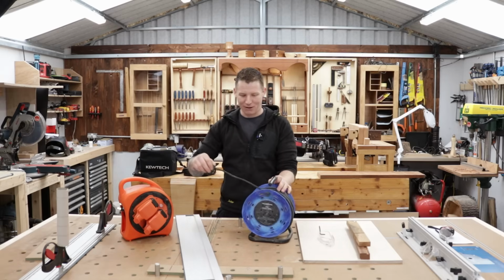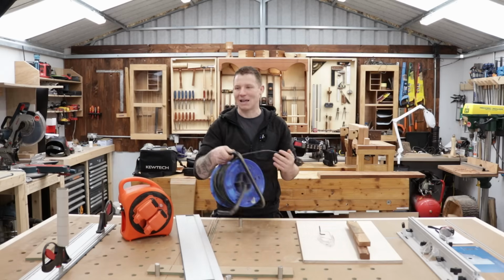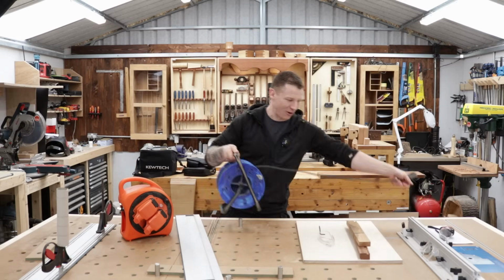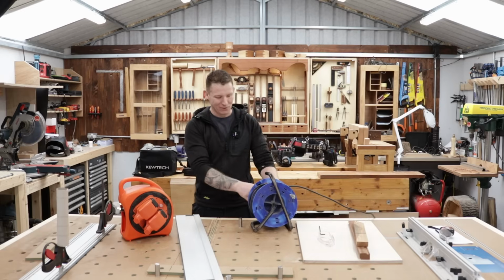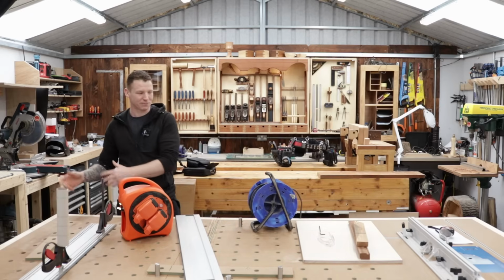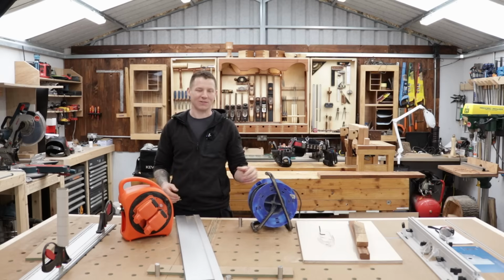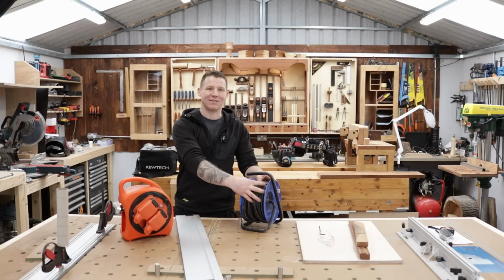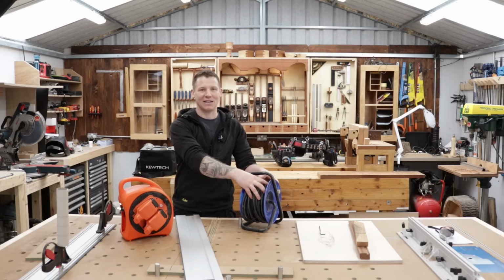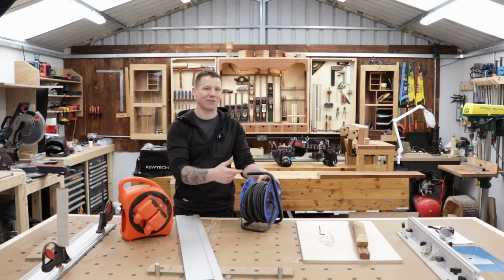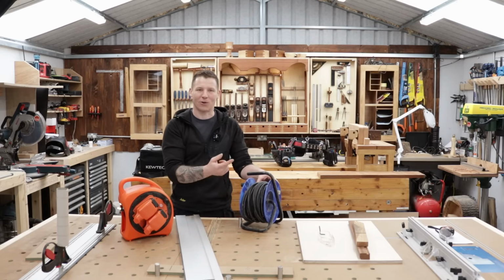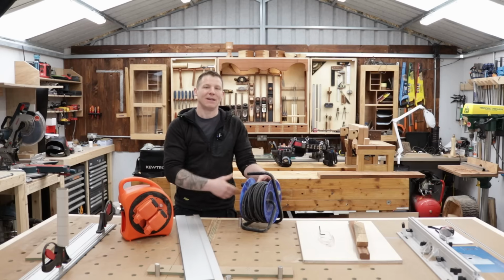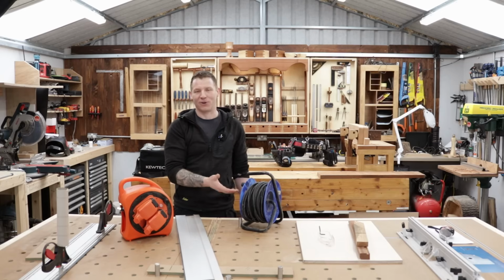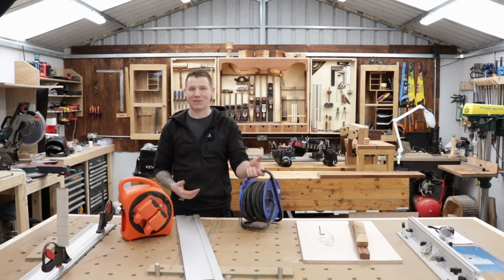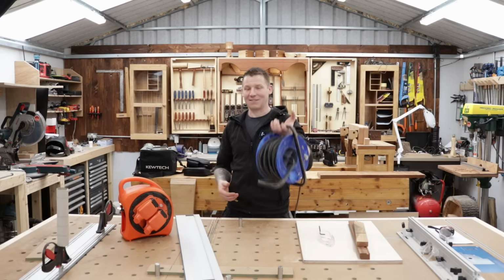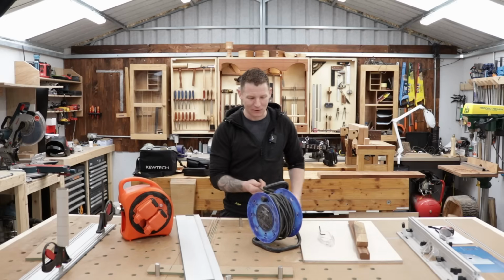So if I only need a meter of cable, and I wanted to plug into a socket there, plug my tool in here and work over here, I'm heating up this cable, and when it's all wrapped up like this, it can't dissipate any heat. So it gets hotter and hotter and hotter. As the heat goes up, the resistance goes up, the hotter this cable will get, and it's a fire hazard and it can melt. So if you have these permanently in place anywhere, that's another danger with them. So I really don't recommend them.